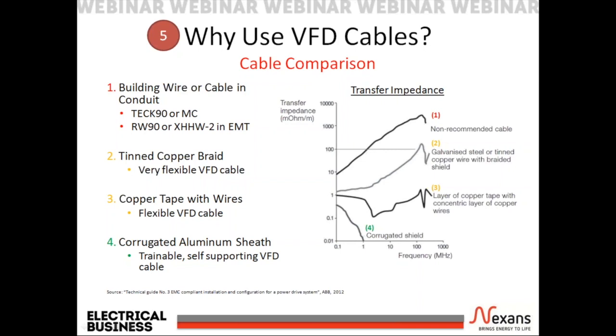A better VFD cable, which is nearly as flexible as tinned copper braid, would be copper tape VFD cables. They offer better electrical performance when compared to the tinned copper braid VFD cables, yet remain flexible. The best electrical performance from a VFD cable is achieved using the corrugated aluminum sheath VFD cable. The compromise, however, is that these cables are not very flexible. In fact, once they're trained into position, they generally retain that shape. This makes these cables somewhat self-supporting, but not suitable for applications requiring flexibility.